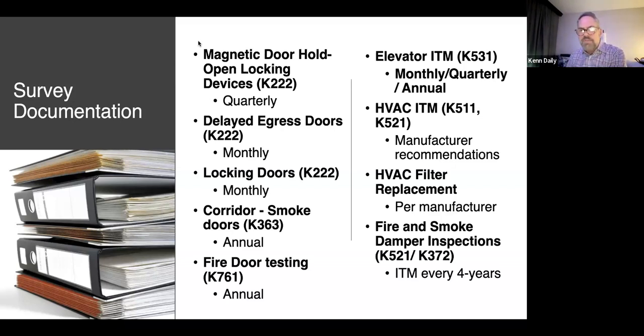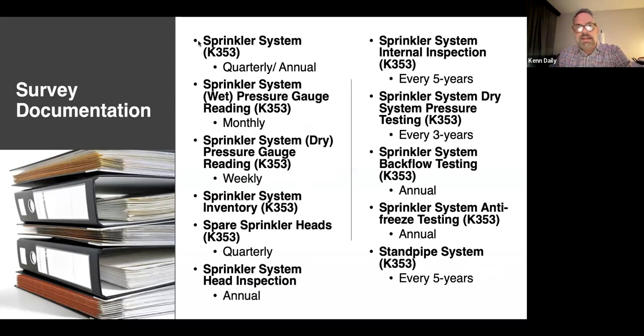And then a hot topic, of course, is smoke and fire dampers. I've seen it a couple places, most cited at K tag 520, K tag 521. You need to know what you have, of course. Do you have a fire or smoke damper? It's going to be important to know. And then from that, you're going to have to make sure you inspect, test, and maintain it, clean it. And then the fusible link in a fire damper, you have to show documentation you either replaced it or cleaned it. So that's every 4 years for skilled nursing facilities that you are getting your dampers inspected, tested, and maintained.